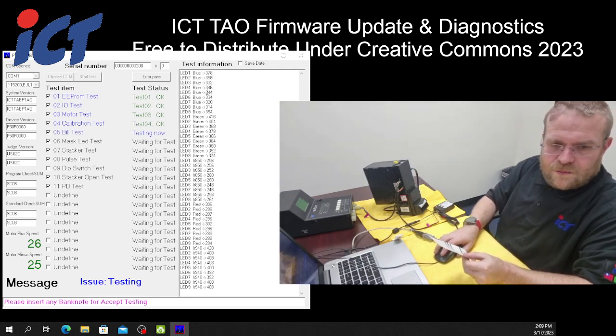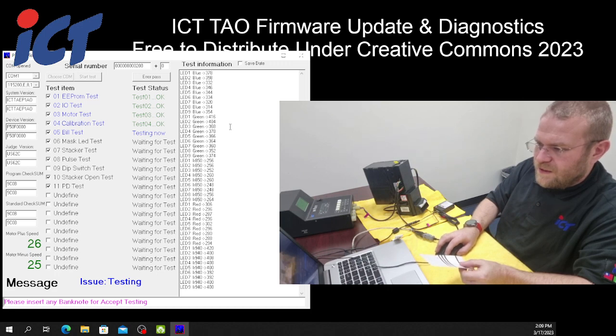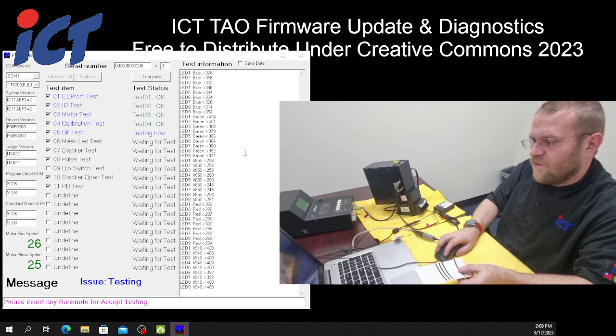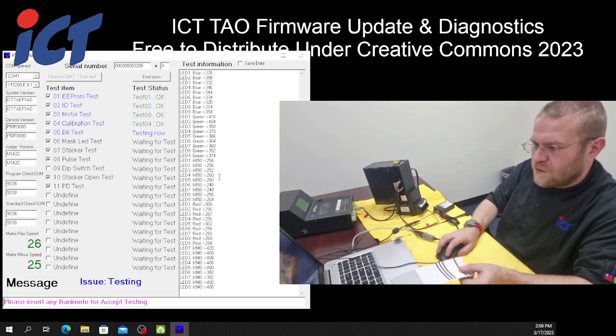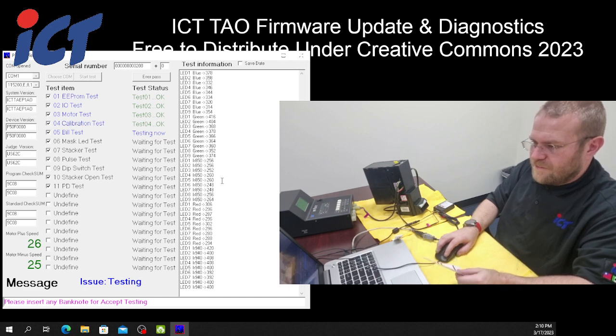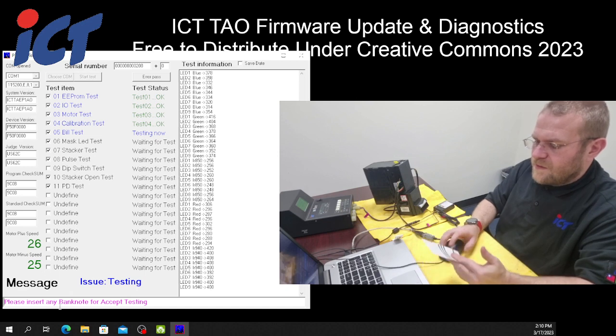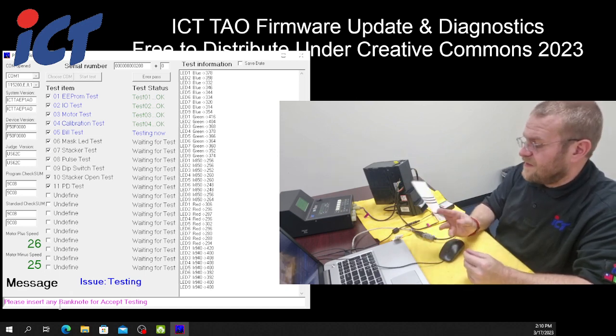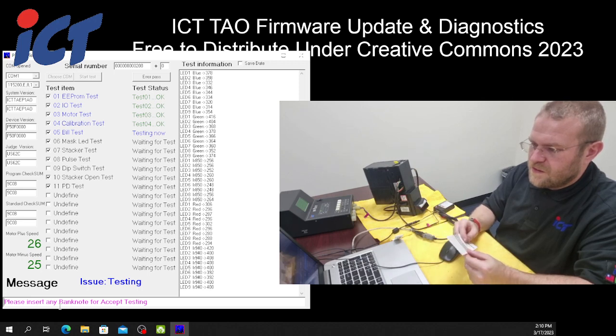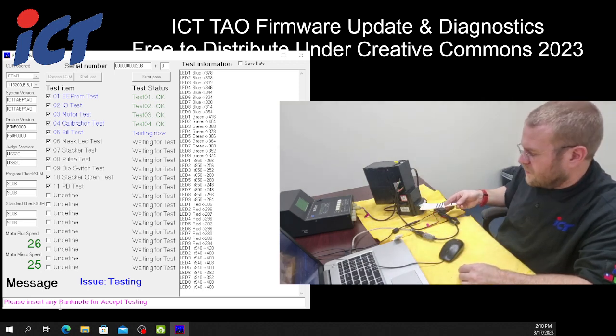If there is any problem in your sensors, it will note them here, like LED 4 in G, overvalue, and it will let you know specifically in this text area which sensors are bad, if they are. On this unit, there are no bad sensors, so it didn't flag it. The next step says to insert any banknote. It's not actually testing money. This test is for the hook sensor. So you can just use your same calibration card to insert it.